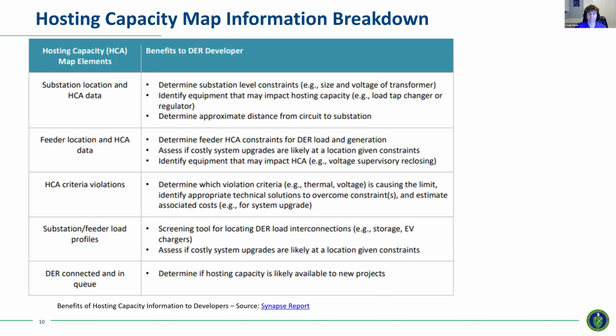So what kind of information is in a hosting capacity map that's really useful? First, substation, locational, and hosting capacity calculated data - what are the constraints, what equipment inside the substation may be impacting hosting capacity. For example, is there a load tap changer on the transformer, is it rated for reverse power flow. Substation location also matters - how close are you to the substation. Generally the closer you are, the higher the hosting capacity because the system is stronger, although not always.